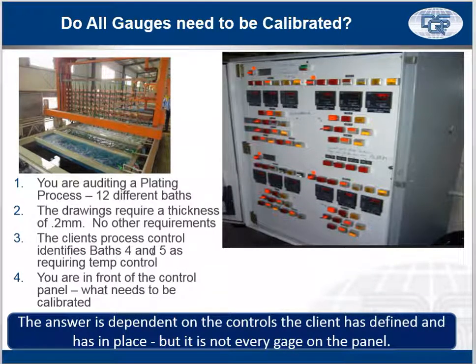So those of you that are plating experts, probably like Dave, are saying, Dave, that was a really simple example and you really kind of downplayed that. But I don't want to go overly complex here. I want to illustrate the point that when you walk up to one of these machines, don't automatically default and say, oh, all these are gauges, so they have to be calibrated. It really matters as to how the process control is being defined. In a case like this, it could have none of them being calibrated if they say, we test every batch for thickness, and they could show you evidence of that sort of control.